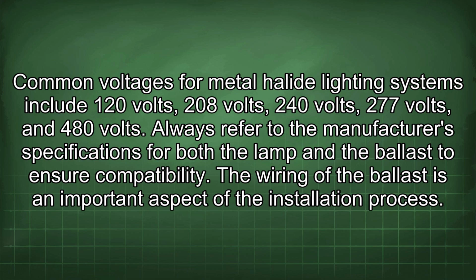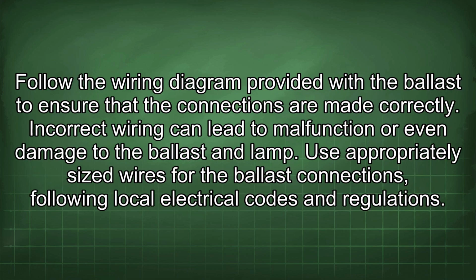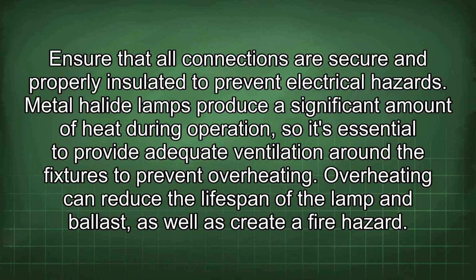The wiring of the ballast is an important aspect of the installation process. Follow the wiring diagram provided with the ballast to ensure that the connections are made correctly. Incorrect wiring can lead to malfunction or even damage to the ballast and lamp. Use appropriately sized wires for the ballast connections following local electrical codes and regulations. Ensure that all connections are secure and properly insulated to prevent electrical hazards.